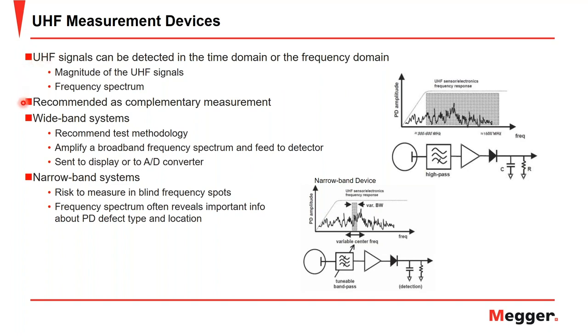And the UHF measurement, or the electromagnetic measurement, is ultimately recommended as the complementary measurement to the electrical or the IEC 60270 conventional method. And again, we were talking about wideband and narrowband. The UHF measurement systems also come in wideband and narrowband systems. Here we have an example of a wideband system, which is the recommended methodology, because you get to see the entire PD signal and not excluding any of the important signal features. And this happens by amplifying the broadband frequency spectrum and feeding it to a detector, which is sent to either a display or an analog digital conversion for display.